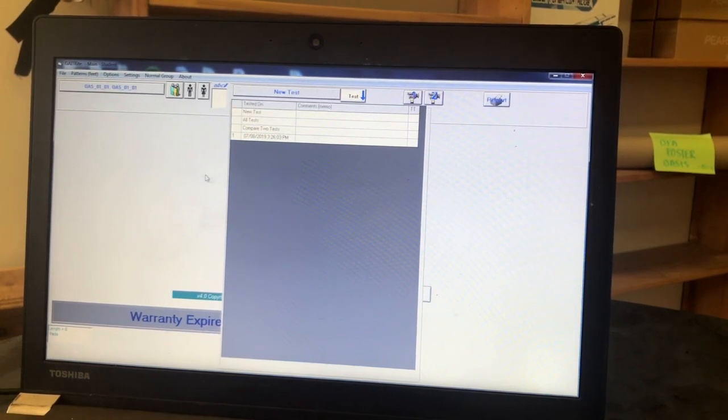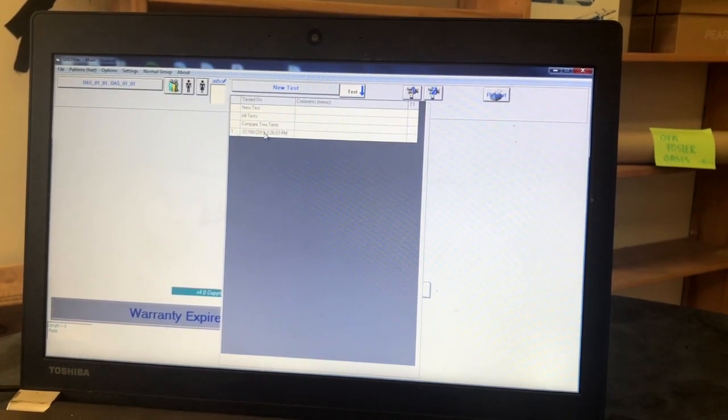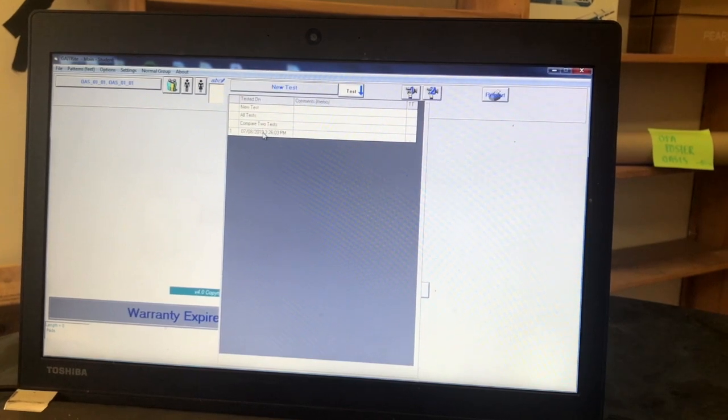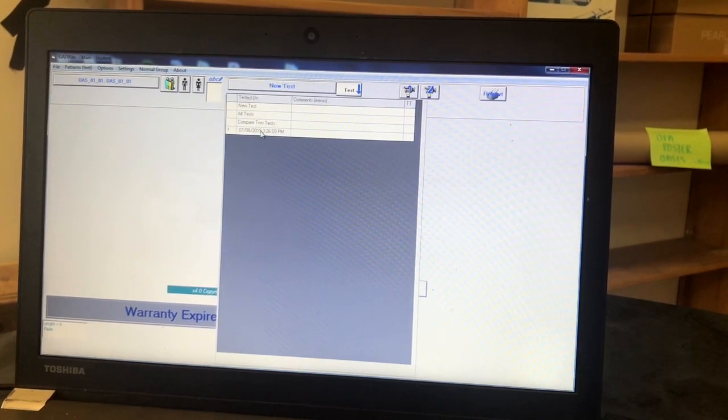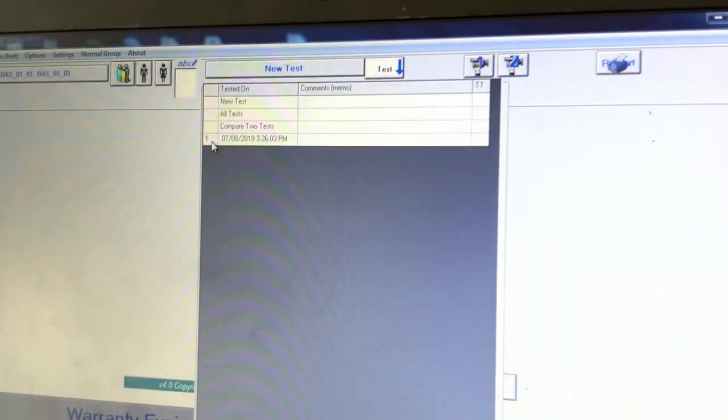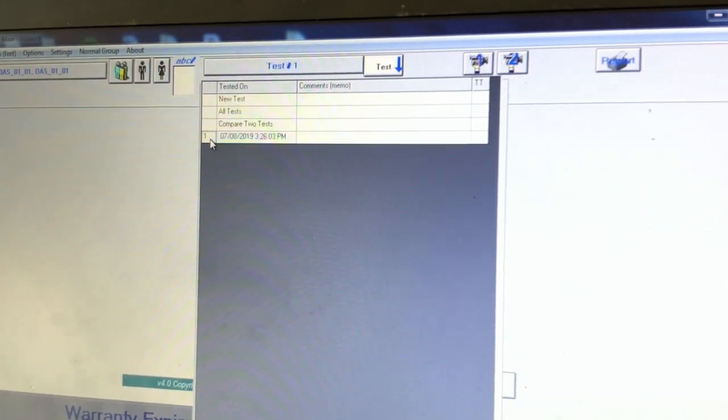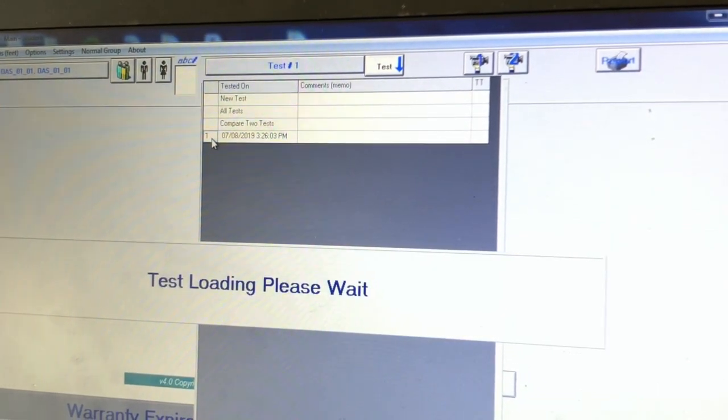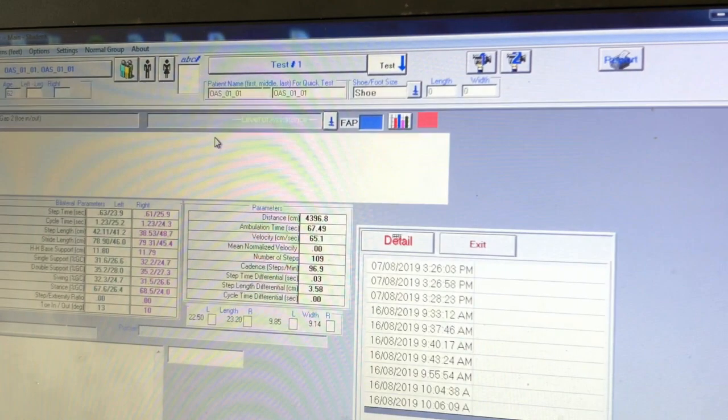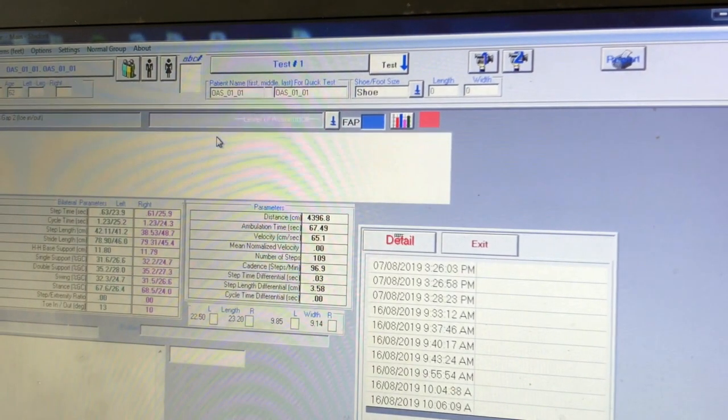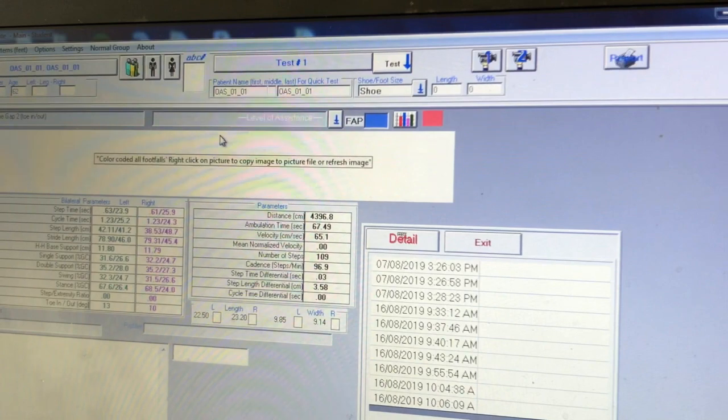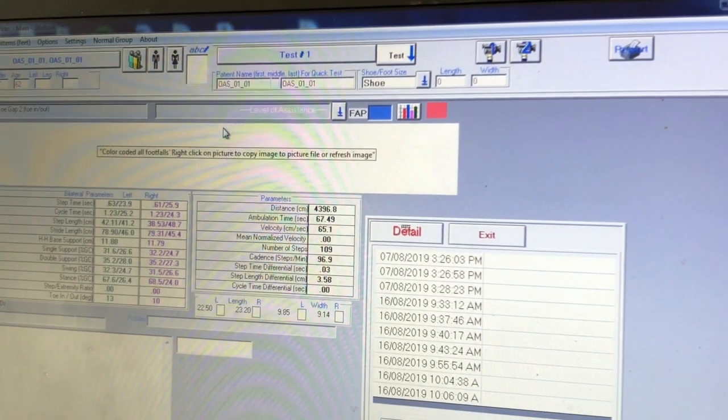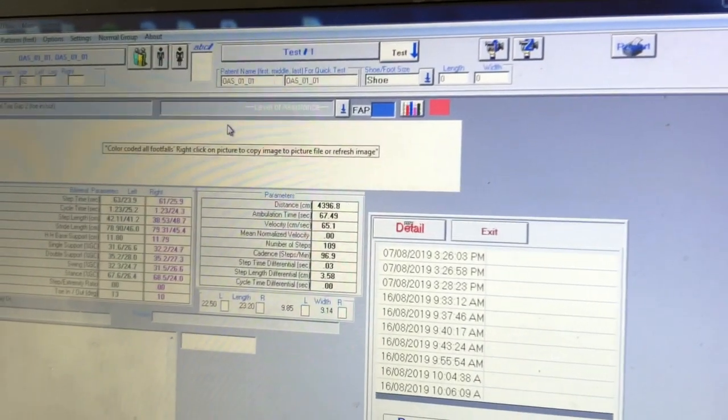Now, the drop-down menu should consist only of one test. Click on the test and the same screen as when data collection was occurring should come up. Only this time, no footprints will be displayed and in the dark gray box on the left, you should see your four walks and the time they were completed listed. What including all four walks in a test has done is average out all of the values for the parameters like step time, cycle time, etc. from all of the four walks.